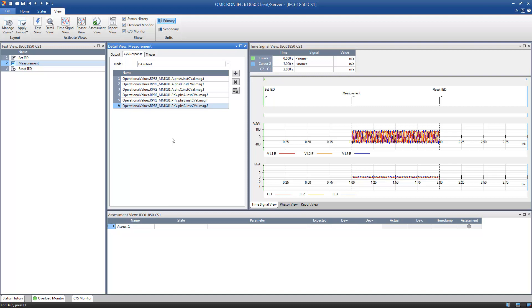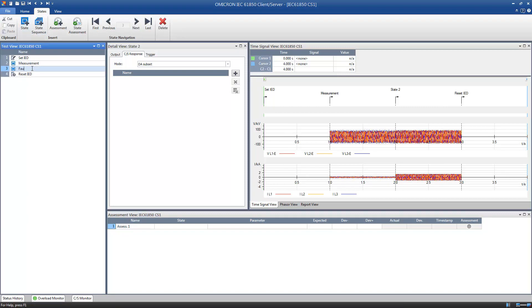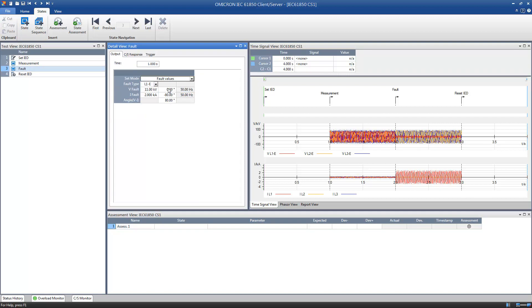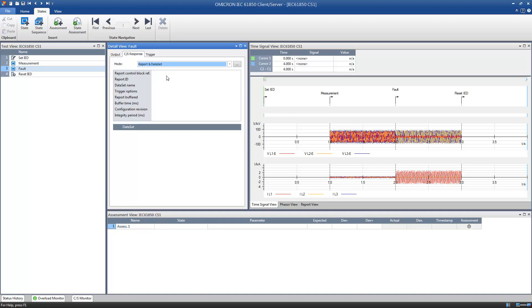In the next step, we configure a fault state to assess the behavior of the IED in terms of client-server communication. We want to test whether a report is sent out as a reaction to the fault and whether the trip signal in the report is properly set to True. We insert a new state with the name Fault and define the fault currents and voltages. In the tab Client-Server Response, there are two possibilities to test reports: with the option Report, you can assess the receipt of a report; with Report and Data Set, you can additionally evaluate the information in the report. For this tutorial, we choose the option Report and Data Set.